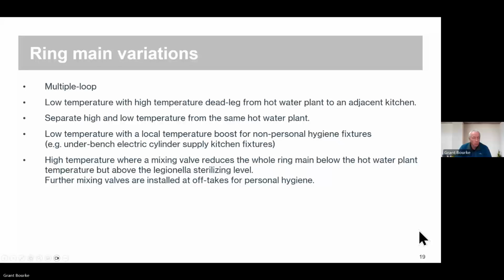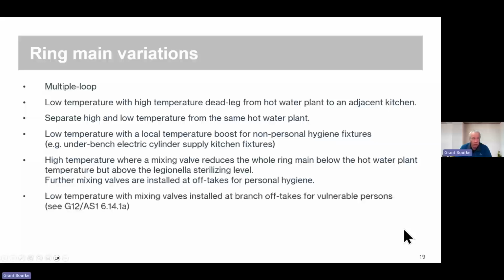I won't mention everyone's favourite system, but we might put a mixing valve in to mix the whole ring main down to 60 or 65 degrees and then have further mixing valves at off-take points for personal hygiene. And obviously, where we've got vulnerable people, we might have a higher temperature ring main and we might mix at those branch off-takes down to 45 degrees for those vulnerable people.